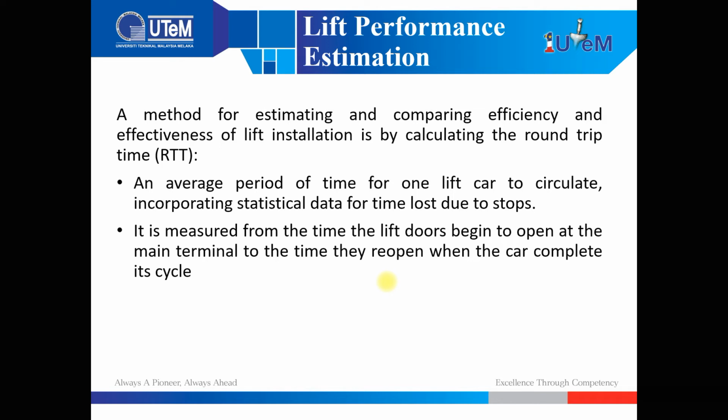Okay, a method for estimating and comparing efficiency and effectiveness of lift installation is by calculating the round trip time. This one is the method to estimate the efficiency and the effectiveness of the lift. Kita nak dapatkan efficiency tu melalui the round trip time. An average period of time for one lift car to circulate, incorporating statistical data for time lost due to stops.